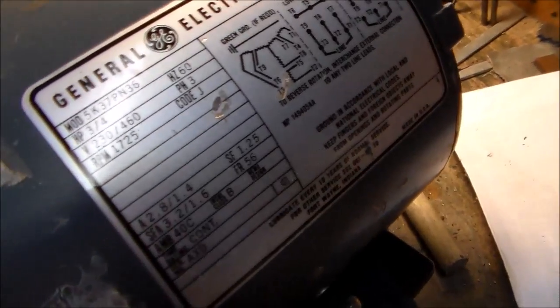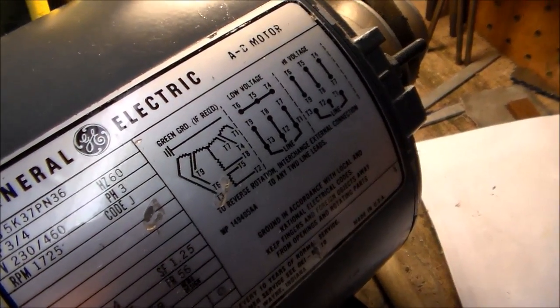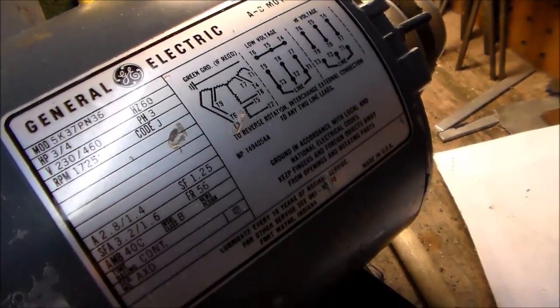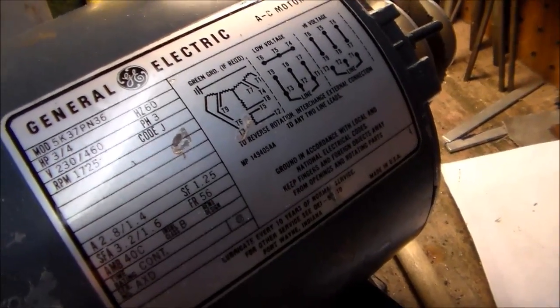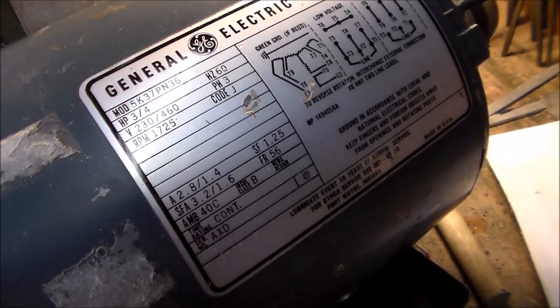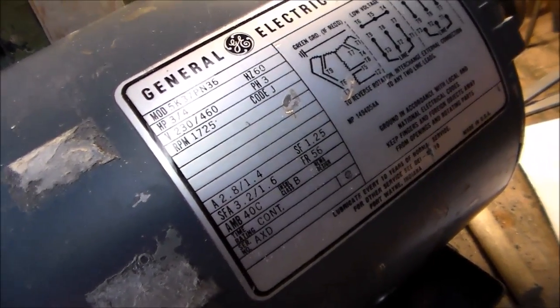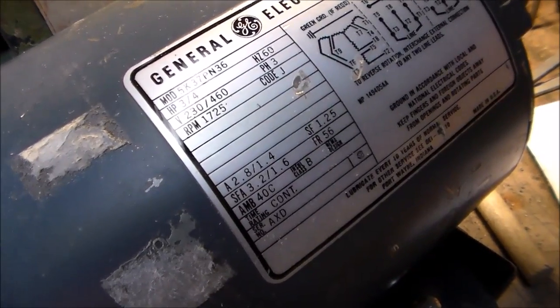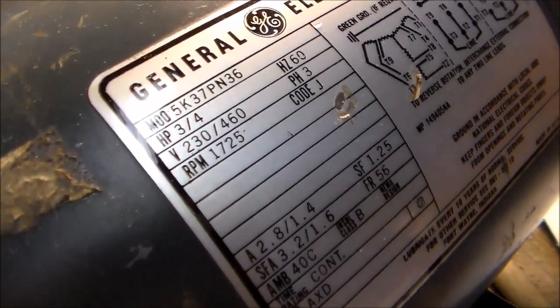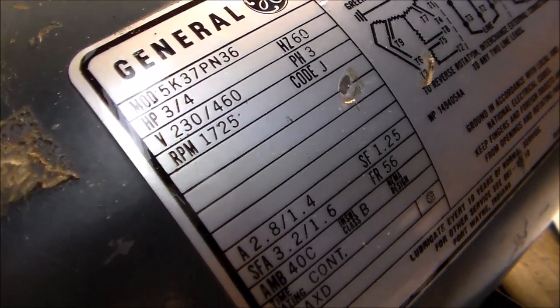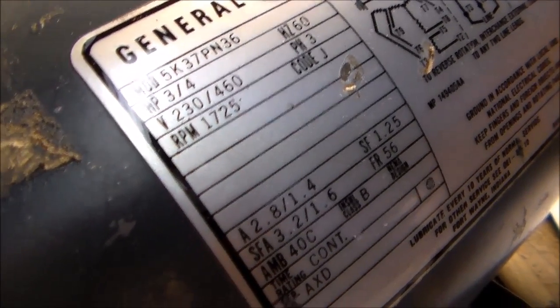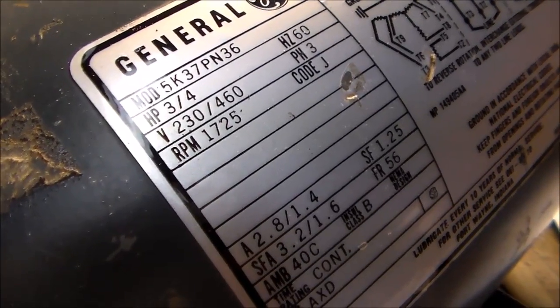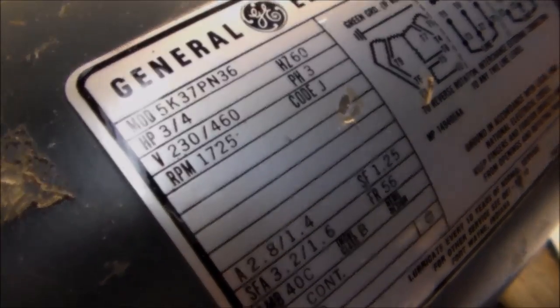All these three phase motors have a wiring connection diagram on the side. Most of the time, these little single phase drives, you're going to use the low voltage connection. You need to get a 240, 220, 240, depending on how it's labeled motor. They'll say like this one says 230 slash 460. Some of them will say 240 slash 480. But that's the kind of motor you're after.